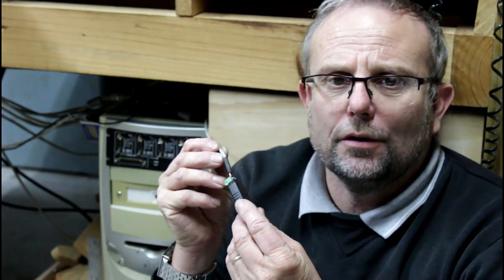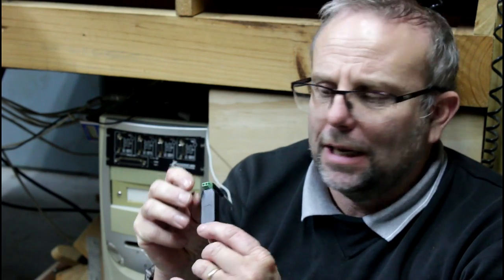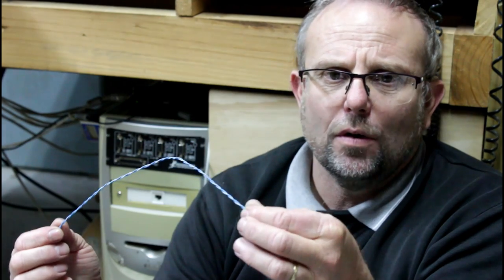This cable here, while it's shielded, I'm using the shield as a screen not to connect the signal. There are two wires inside this cable. The RS485 protocol is a balanced circuit, it needs a twisted pair of wires like this here.